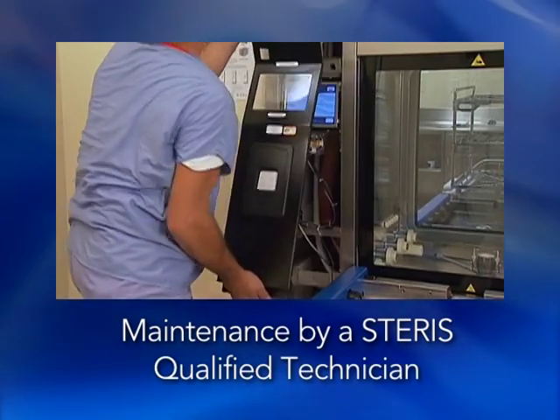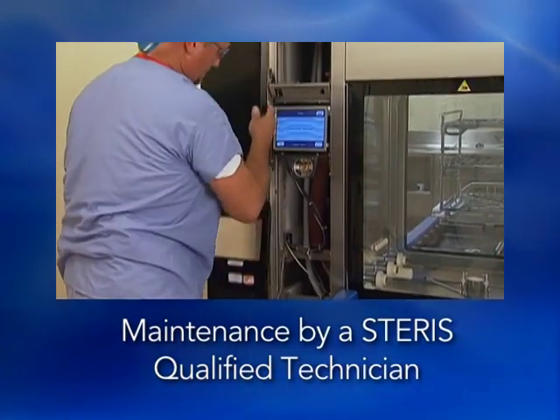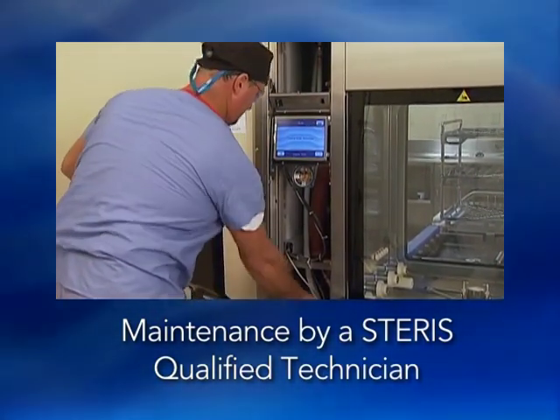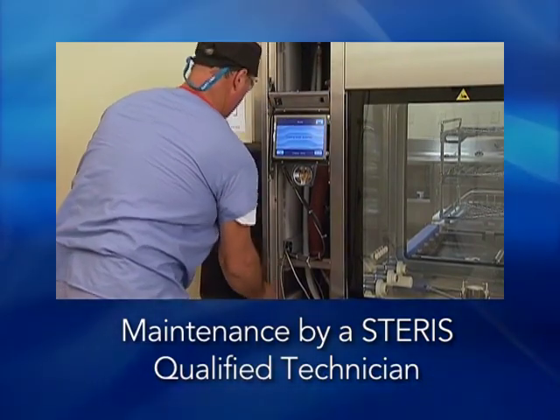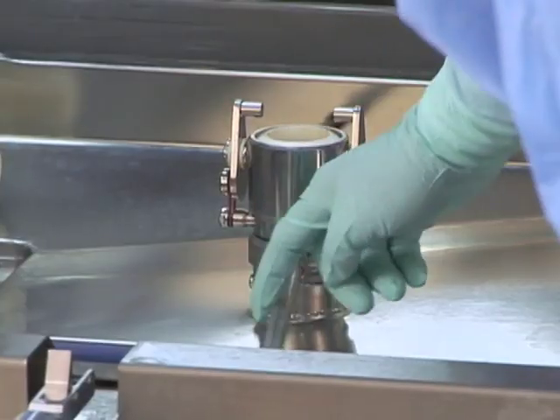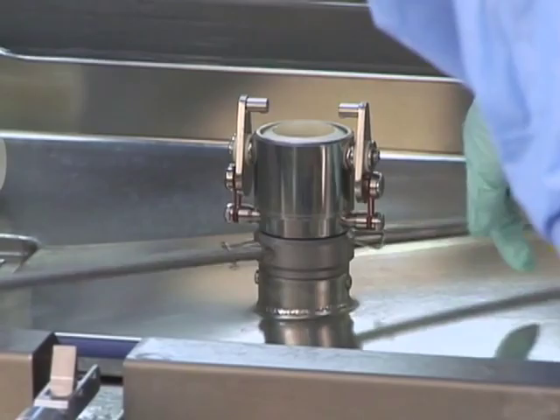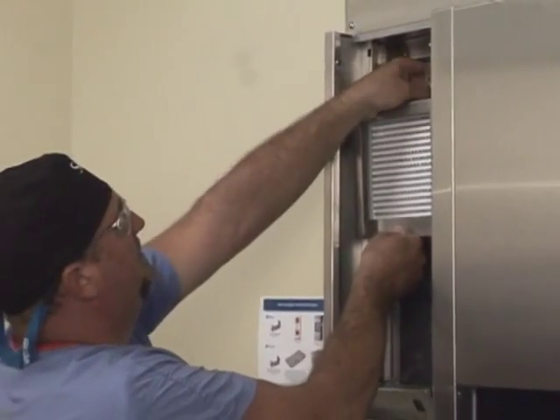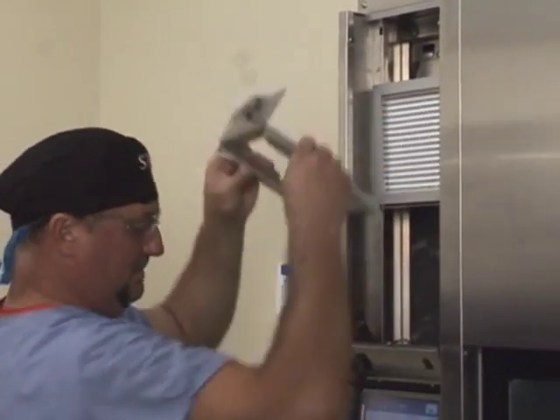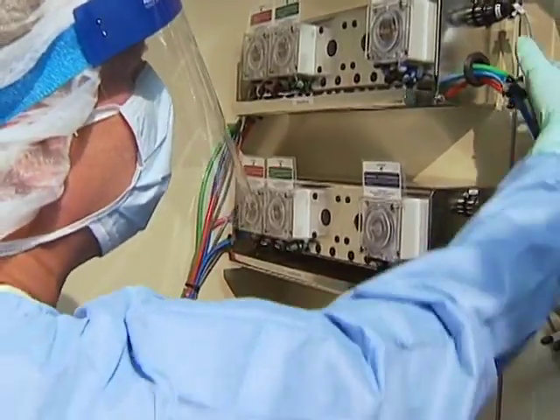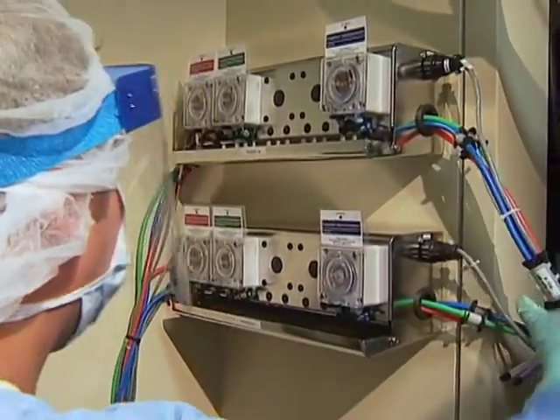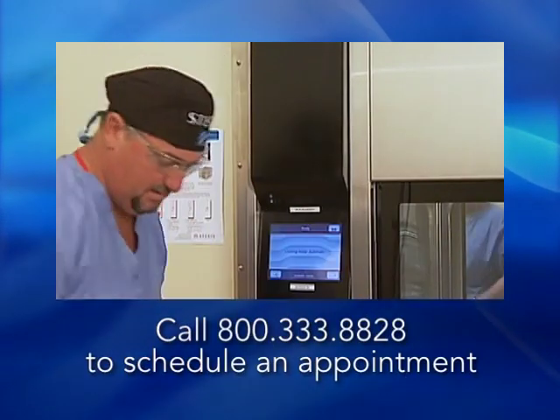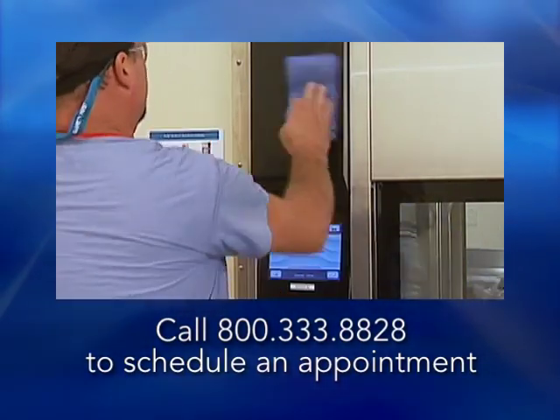Certain preventative maintenance activities must be done by a STERIS service technician or a STERIS-trained service technician in your facility. These activities include inspecting and cleaning the rotary spray arm assemblies, HEPA filter verification and replacement, and chemical injection pump and squeeze tube verification.